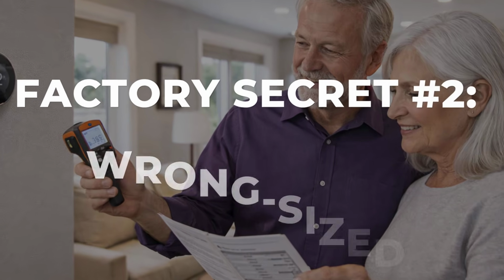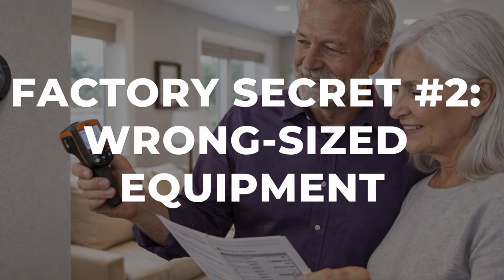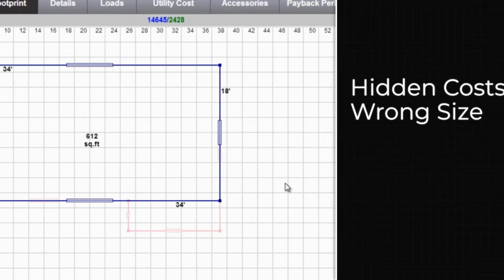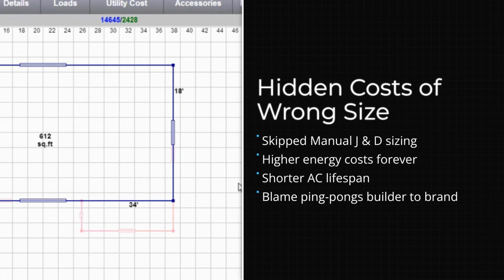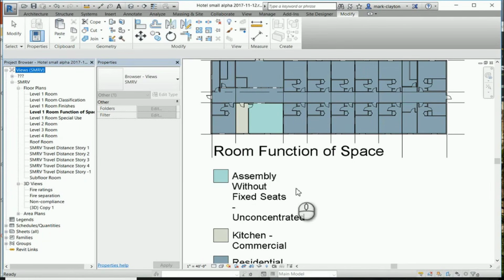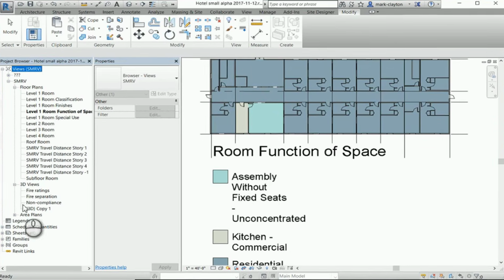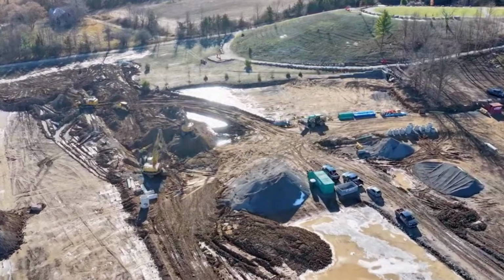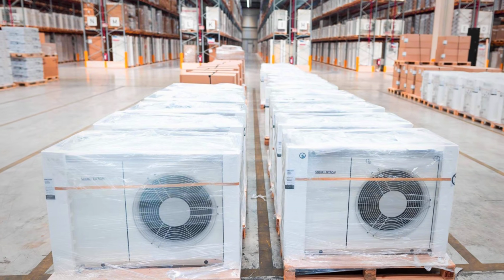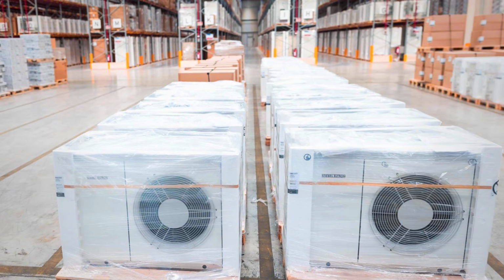Factory secret number 2. Your system was the wrong size before you moved in. Proper sizing requires Manual J and Manual D calculations, software analysis of the home's square footage, insulation, windows, and climate zone. Most codes require them. In practice, volume builders skip them and install whatever the subcontractor has in inventory.